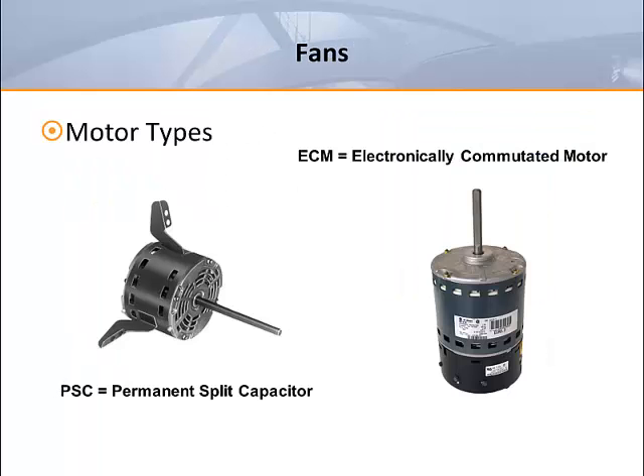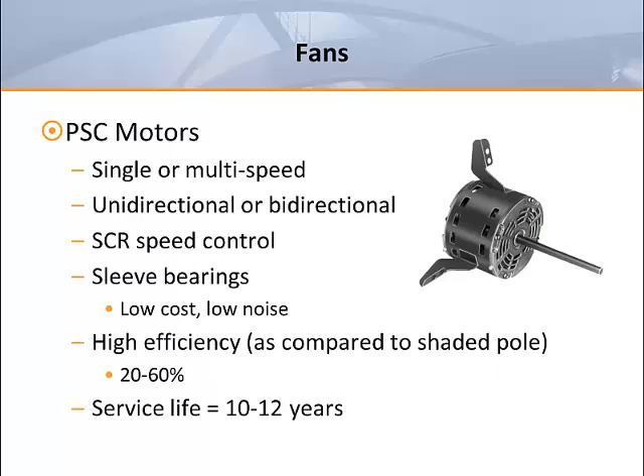Now let's look at motors. There are two types of motors used in terminal units: PSC and ECM. These motors have different operating limitations and features, so they should be selected and applied differently. Permanent split capacitor motors, or PSCs, for many years were the only motor choice. These motors can be single speed or multi-speed, unidirectional or bidirectional. They use a silicon controlled rectifier or SCR speed control to balance the fan. They typically have sleeve bearings for low cost and quiet operation. These motors are classified as high efficiency motors, but only when compared to shaded pole motors. The efficiency is 20–60% and is directly proportional to the speed, so as the speed is reduced, the efficiency is also reduced. When properly selected and installed, PSC motors can expect to have a service life of 10–12 years. Failure usually occurs due to sleeve bearing wear.